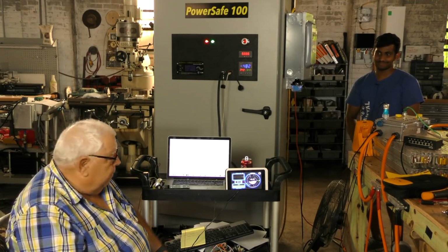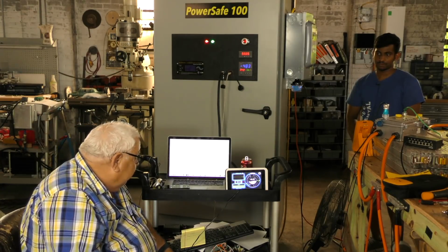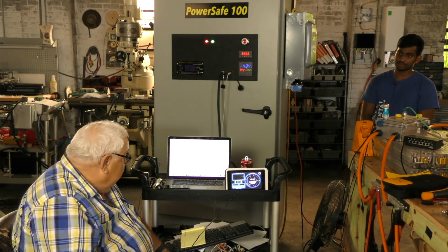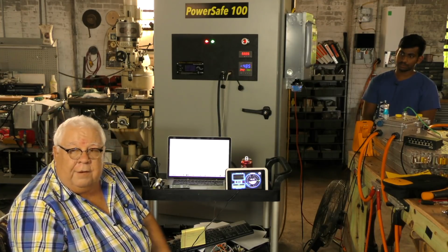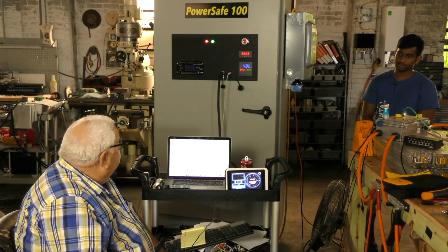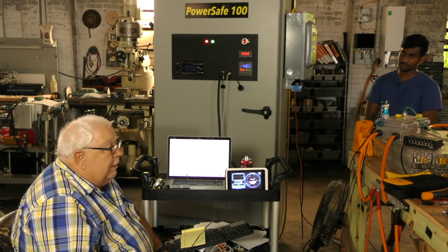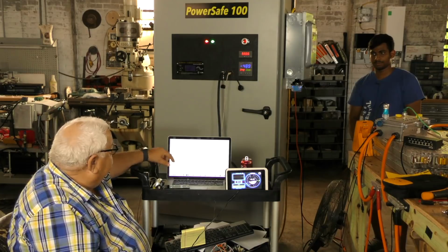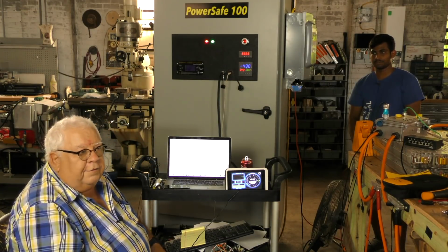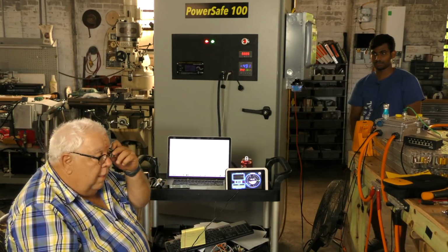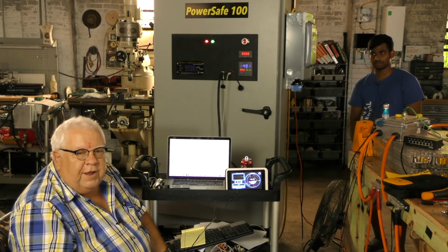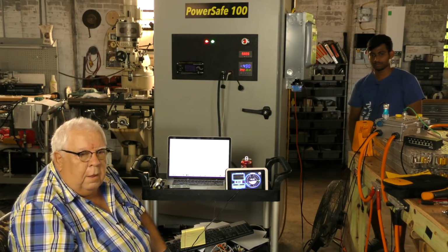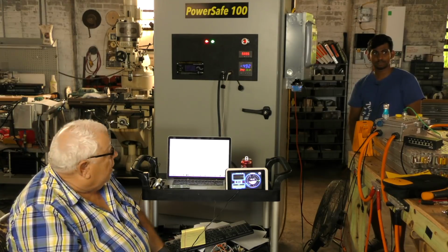When we provide them with 244.1 volts, 5 minutes and 12 seconds later they respond by outputting 244.9 volts and pumping, in this case, about - we're up to 360 - about 500 watts of charge into our batteries, charging at 8.85 amps. So we can scale that up to whatever you want. That's with 3 panels and 3 Enphase IQ7x microinverters. With 40 panels, we can be putting quite a bit of current into this battery.